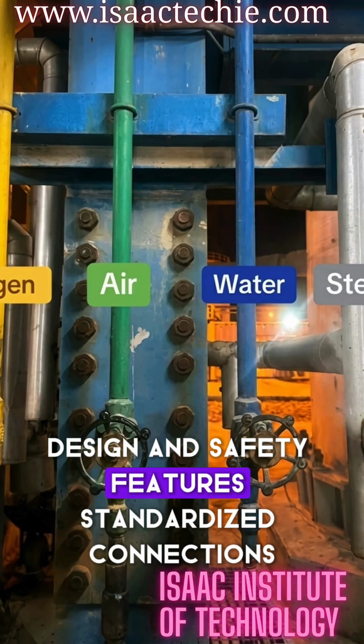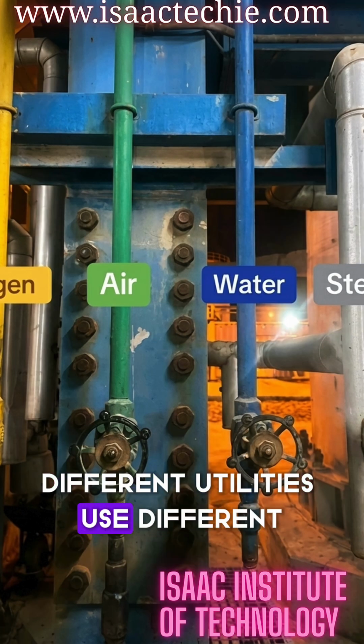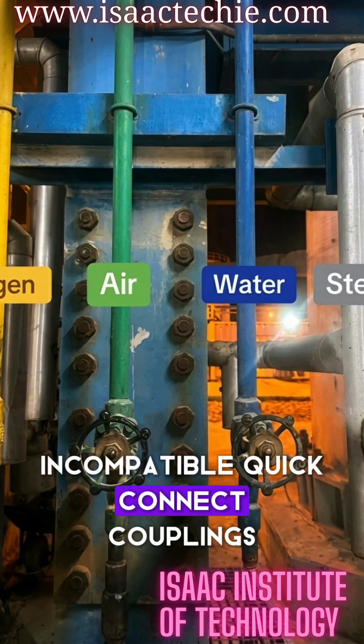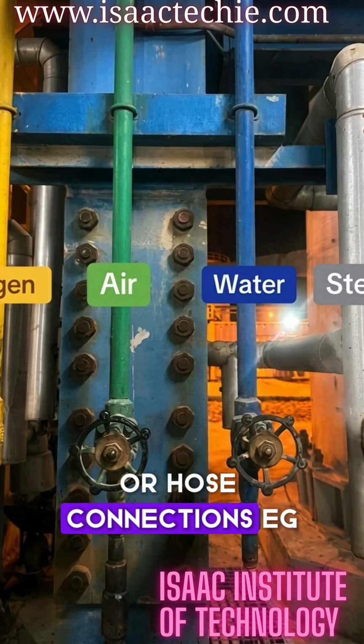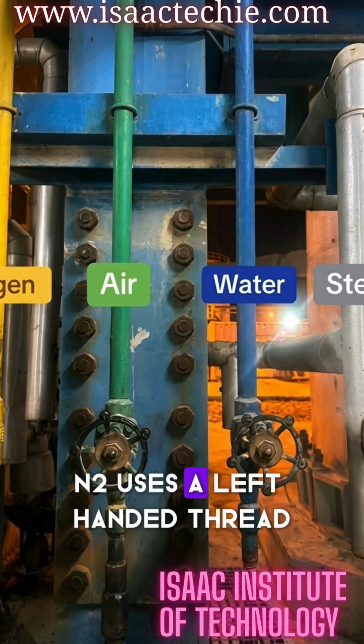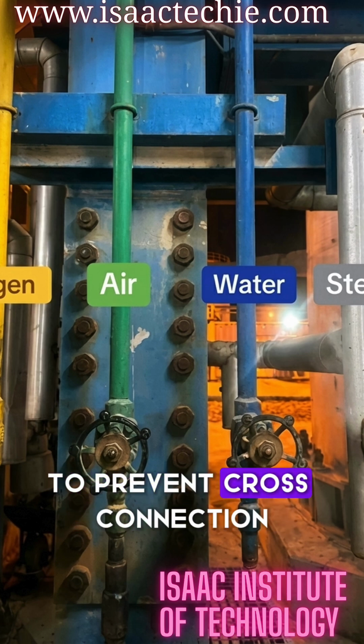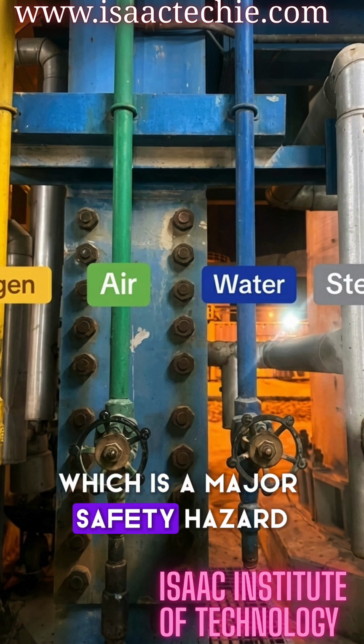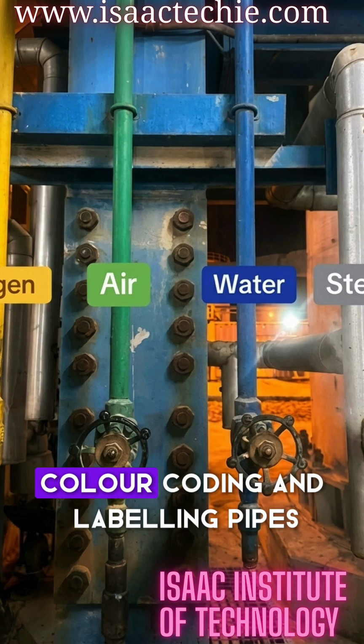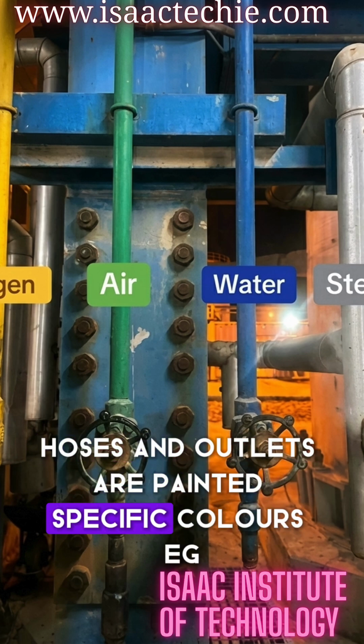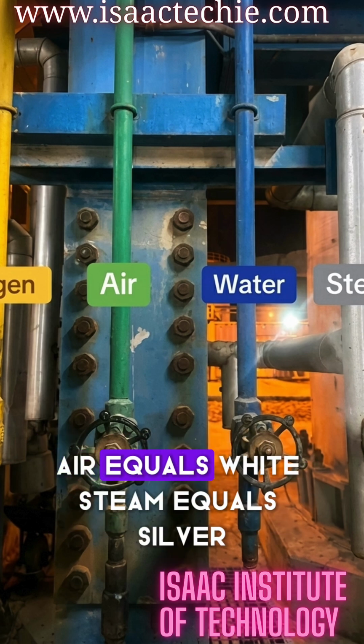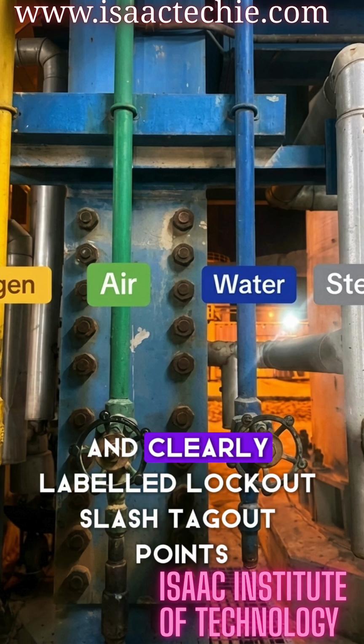Design and safety features. Standardized connections. Different utilities use different, incompatible quick connect couplings or hose connections, e.g., N2 uses a left-handed thread to prevent cross-connection, which is a major safety hazard. Color coding and labeling. Pipes, hoses, and outlets are painted specific colors, e.g., air equals white, steam equals silver, nitrogen equals yellow, and clearly labeled.